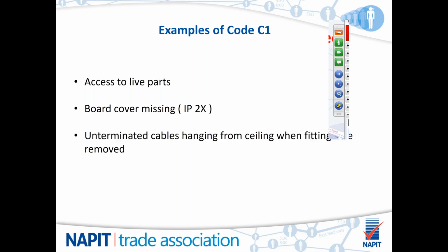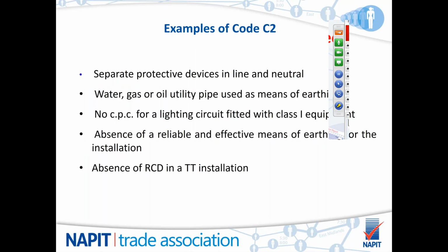Okay, so let's have a look at some examples for codes then. Now then, examples, the list is endless really. No two installations are the same, and like I was trying to say before, a code 1 is something that, can I touch electricity? And if that's the case, then it's going to be code 1. So access to live parts, code 1. Let's say the board cover's missing, so I can get my fingers in, IP2X. And also, let's say there's unterminated cables hanging from the ceiling, where, for instance, a light fitting's been taken down and the cable's just been left with nothing done to it.